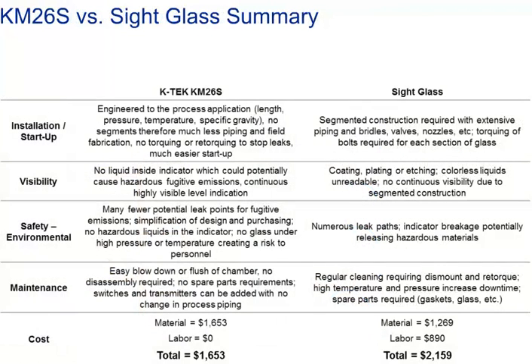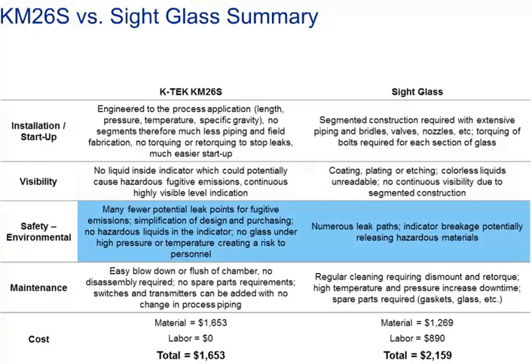A side mount offers continuous visibility as opposed to the segmented construction of sight glasses. Other advantages include cost savings over complex bridle assemblies with additional valves and leak points. Sight glasses are prone to discoloring, plug connections, leaks, glass erosion, cracks, and valve problems. All of these potential problems are eliminated by using a magnetic level gauge.